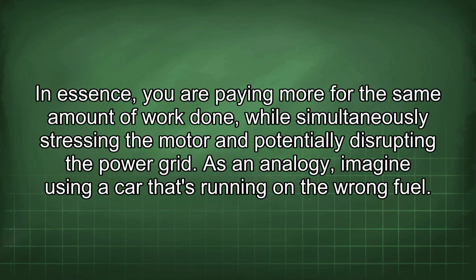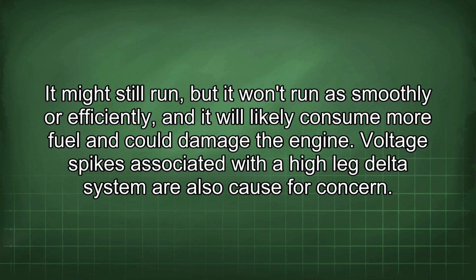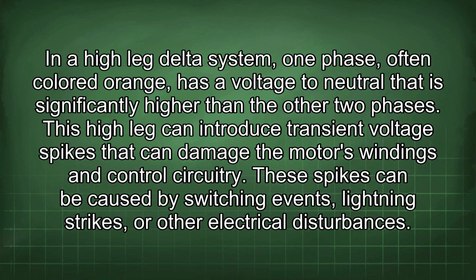In essence, you are paying more for the same amount of work done, while simultaneously stressing the motor and potentially disrupting the power grid. As an analogy, imagine using a car that's running on the wrong fuel. It might still run, but it won't run as smoothly or efficiently, and it will likely consume more fuel and could damage the engine. Voltage spikes associated with a high-leg delta system are also cause for concern. In a high-leg delta system, one phase, often colored orange, has a voltage to neutral that is significantly higher than the other two phases. This high leg can introduce transient voltage spikes that can damage the motor's windings and control circuitry.